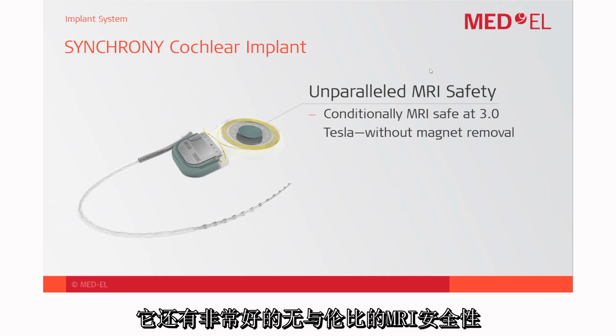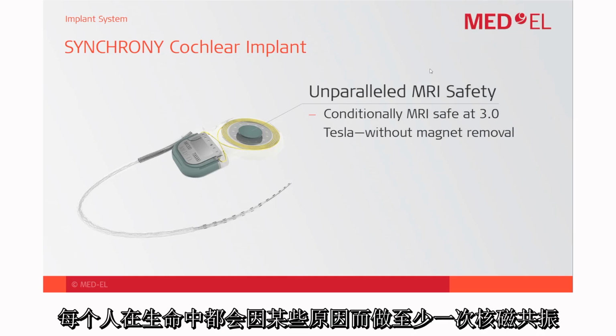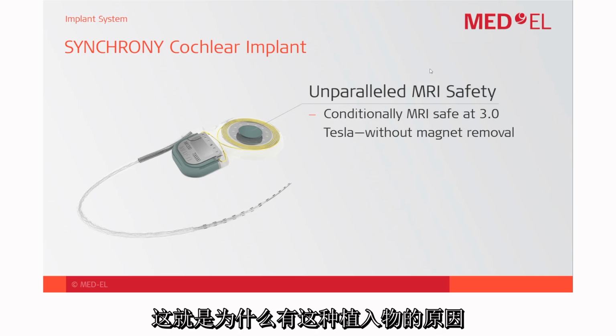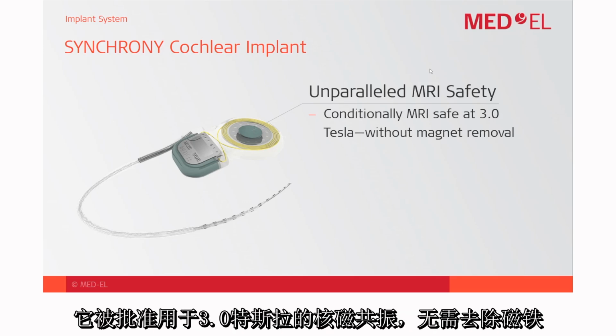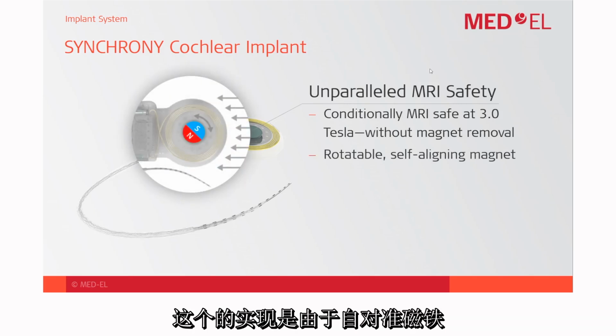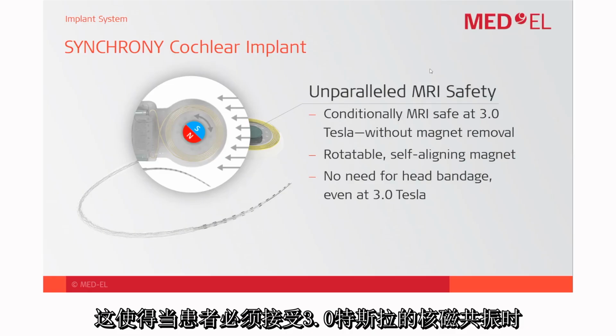Very nice, unparalleled MRI safety, because now we know that every one of us in our lifetime is going to have at least one MRI for some reason, not really because of the cochlear implant itself. That is why this implant is now approved for 3 Tesla MRI without the need of magnet removal. This is possible because of the self-aligning magnet. The polarity of the magnet is not axial, it's now diametric, and that enables this magnet to rotate and self-align itself to the magnetic field in the MRI scanner. And this means there is no requirement of any head bandage when the patient has to undergo a 3 Tesla MRI.